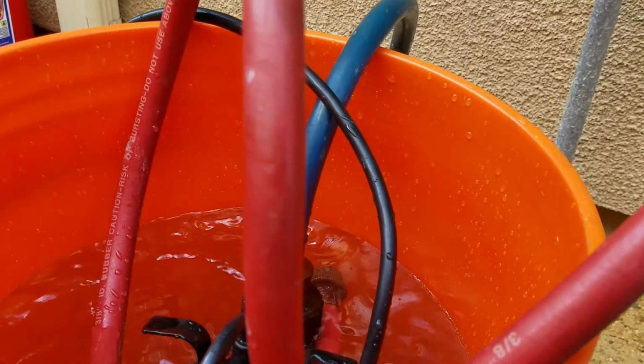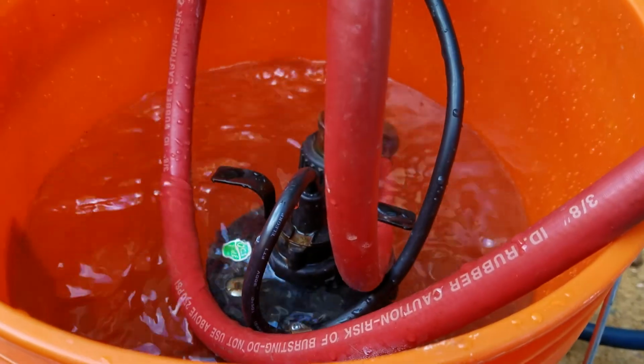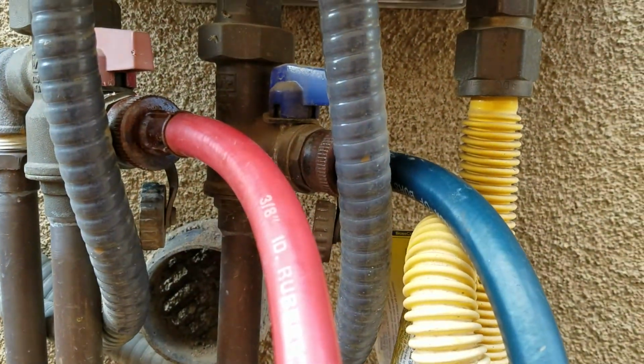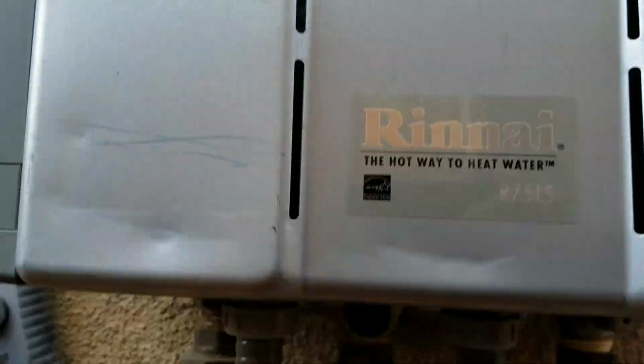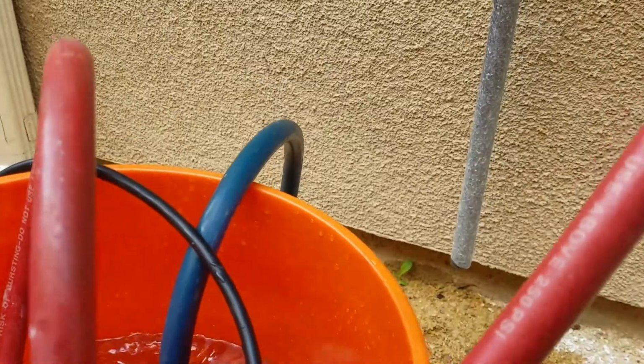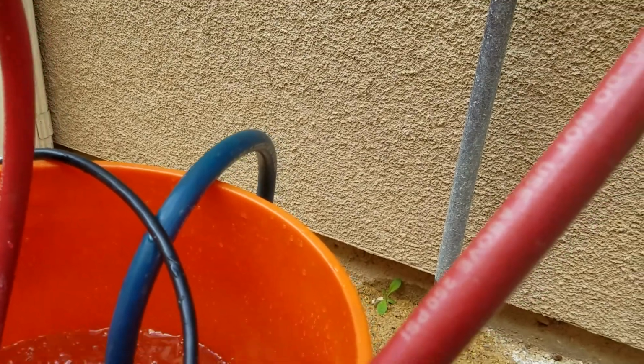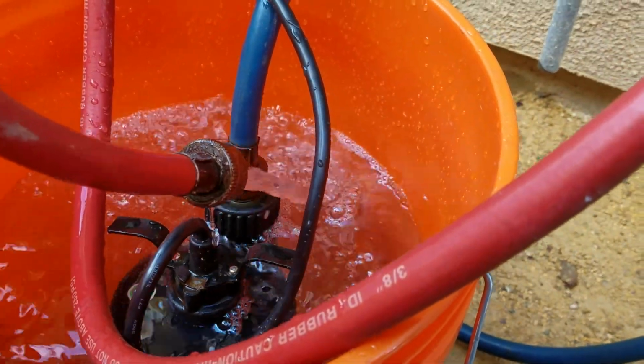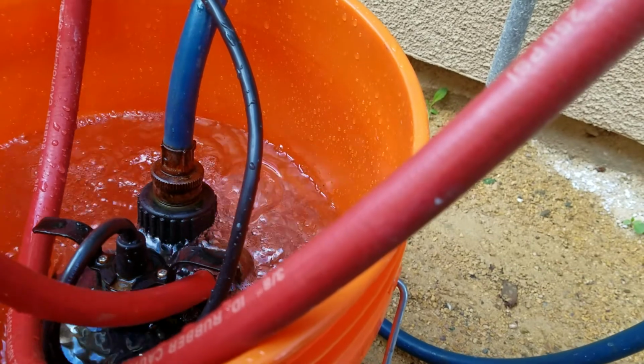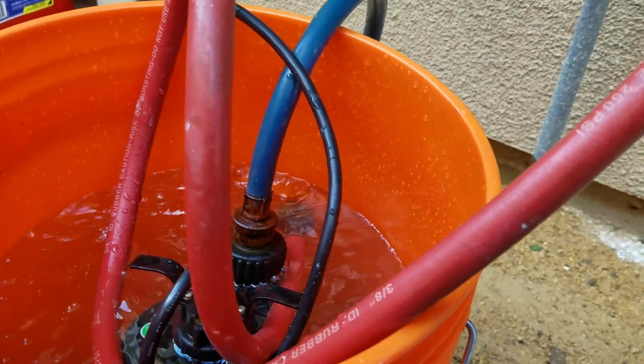So the pump is actually drawing the vinegar out of the bucket, sending it up through the cold side, through the heat exchanger, back out the hot side, and dumping out here in the bucket. You can see right now that's what it's doing, and this vinegar is cleaning out the scale in the heat exchanger.